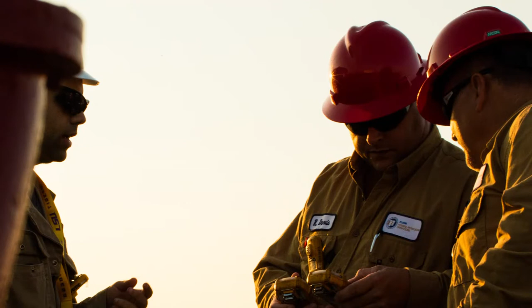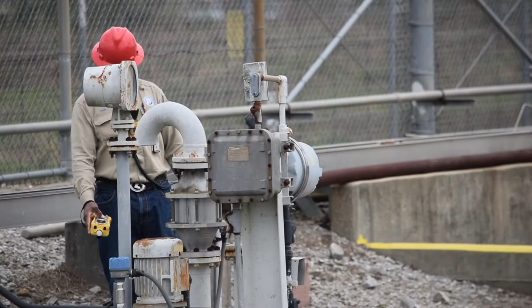Personal protective equipment such as H2S alarms or crickets are to be worn by all individuals that conduct work within designated areas as well as during tasks identified through a hazard analysis as having the potential to expose workers to H2S. Personal H2S monitors warn the user when hydrogen sulfide gas exceeds an alarm set point. Alarm set points shall be set at 10 parts per million for the low alarm and 15 parts per million for the high alarm.